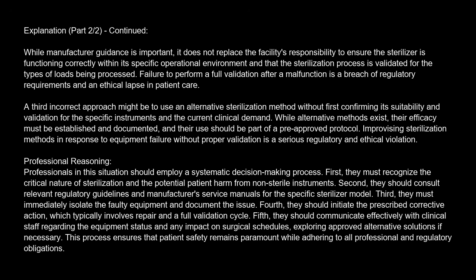Professional reasoning. Professionals in this situation should employ a systematic decision-making process. First, they must recognize the critical nature of sterilization and the potential patient harm from non-sterile instruments. Second, they should consult relevant regulatory guidelines and manufacturer's service manuals for the specific sterilizer model. Third, they must immediately isolate the faulty equipment and document the issue. Fourth, they should initiate the prescribed corrective action, which typically involves repair and a full validation cycle. Fifth, they should communicate effectively with clinical staff regarding the equipment status and any impact on surgical schedules, exploring approved alternative solutions if necessary. This process ensures that patient safety remains paramount while adhering to all professional and regulatory obligations.